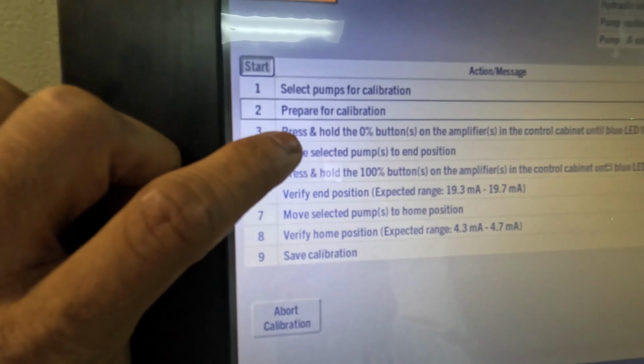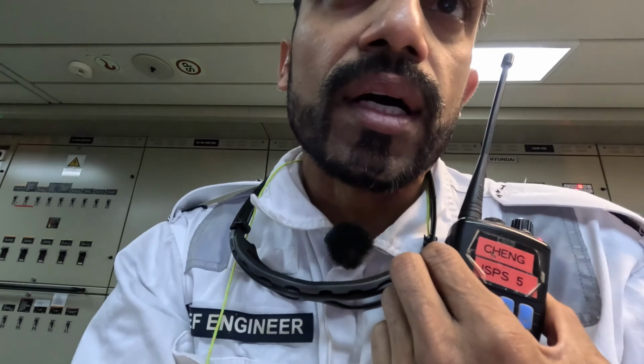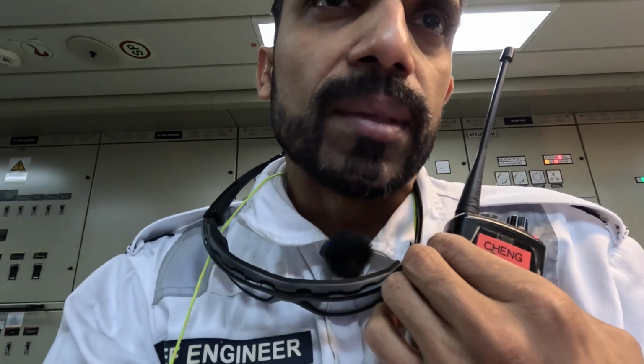You see the pressure is about 236 bar. Now it is asking us to press and hold the 0% button till the blue LED lights up. Rohit, can you press the 0% button on the amplifier until the blue LED flashes? Pressing 0% button. Blue light now flashing. Copy that, blue light flashing. Okay, can you release the button, please? So now we'll move to the next step. You press done. Now move the pump to the end position, by pressing this button.